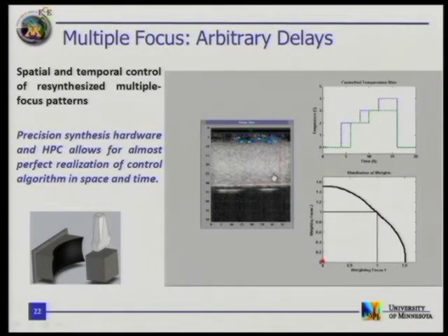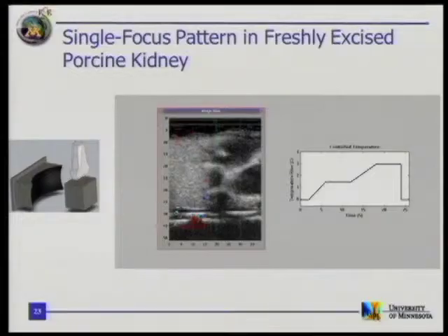This is just a quick explanation of what happens here. Why am I excited about this? Because the corrections from frame to frame are a very small change in amplitude and a very small change in phase. It's because of that new driver that we're able to achieve these small changes, and that happens dynamically from frame to frame as the controller asks for different changes in amplitude. So we can map anywhere in this space with very high precision to maintain very precise control of the heating pattern.